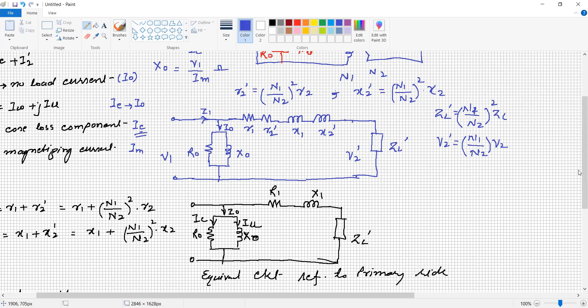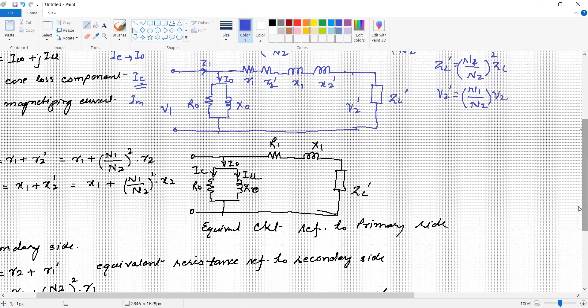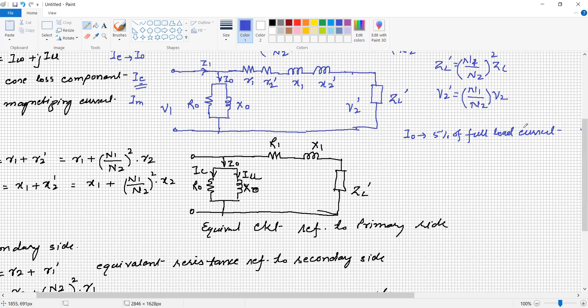The no-load current I0 is nearly 5 to 7% of full load current. The reason is that it only handles iron losses and the magnetic flux in a closed magnetic circuit. Whereas for a three-phase induction motor there is an air gap and a rotating part, so windage and frictional losses exist, making the no-load current of an induction motor higher compared to a transformer of the same capacity. So the no-load current of a transformer is very small compared to the load current.